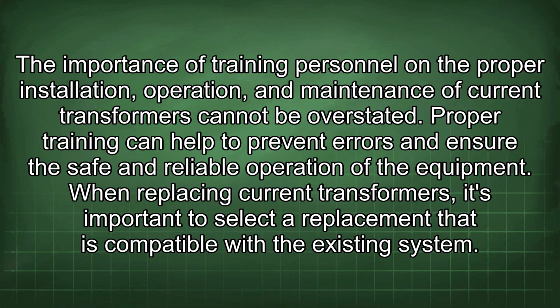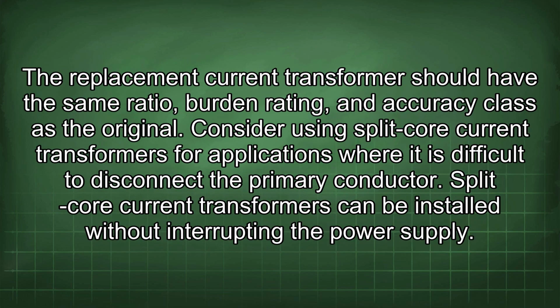When replacing current transformers, it's important to select a replacement that is compatible with the existing system. The replacement current transformer should have the same ratio, burden rating, and accuracy class as the original. Consider using split-core current transformers for applications where it is difficult to disconnect the primary conductor. Split-core current transformers can be installed without interrupting the power supply.